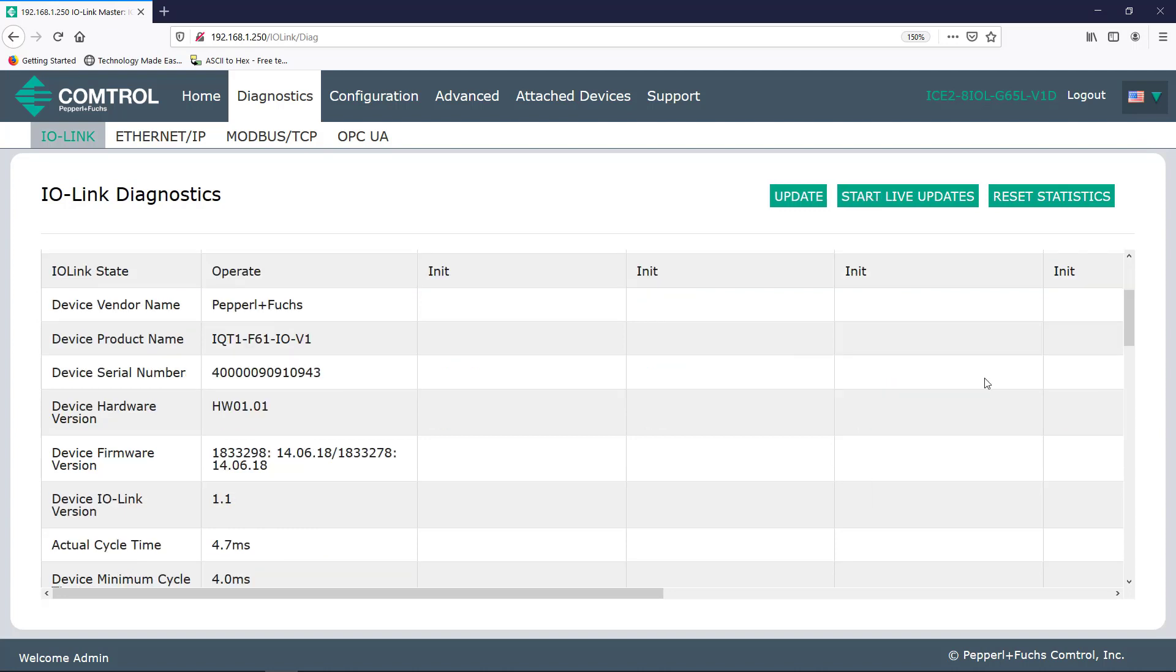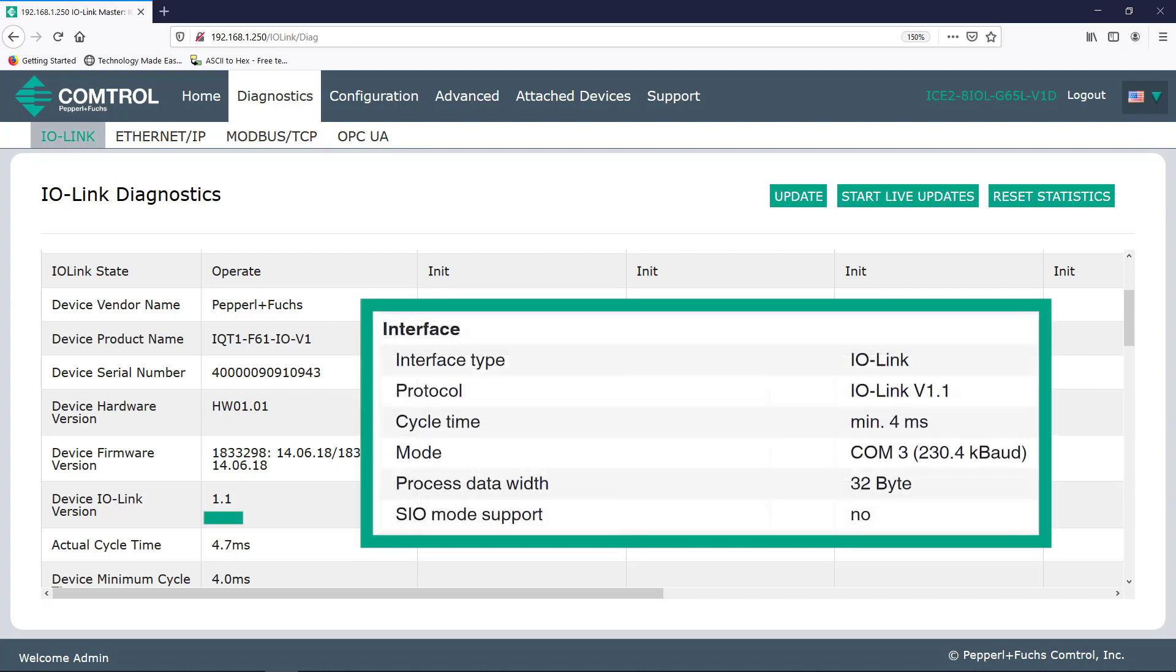So now we see that the IO-Link version is 1.1. And I know this is correct because I can verify it against the data sheet or the product manual. As of January 2017, all new devices made need to be version 1.1. The older and original version is 1.0. Version 1.1 allows more storage, faster communication, and the ability to store parameter settings. Our ICE blocks are version 1.1 and they work with devices from either version.